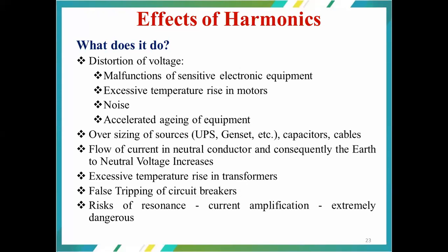Then there is the flow of current in the neutral conductor, which is a predominant effect of these harmonic components. This flow of current in the neutral causes a neutral potential rise, which may lead to fire hazards. Similar to the electric motors, there is excessive temperature rise in the transformers. As I already mentioned, if we study the transformer connected to data centers or any larger IT load, the life is going to get reduced, and derating of the transformers is the major concern. There is also false tripping of the circuit breakers due to the presence of transients from these harmonics or their subcomponents. And the risk of resonance will be there. Resonance may occur due to frequency matching, and due to the resonant condition, current amplification may occur, which will result in dangerous conditions for the transmission networks or the machines.